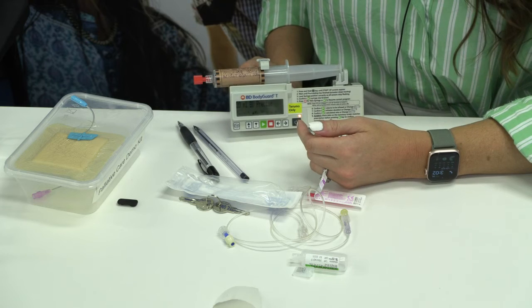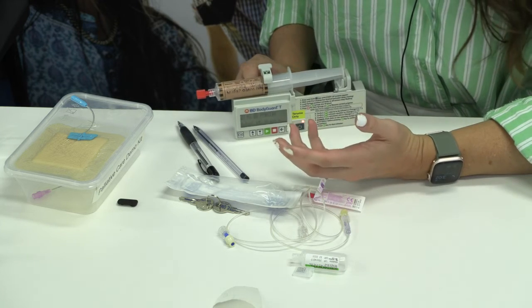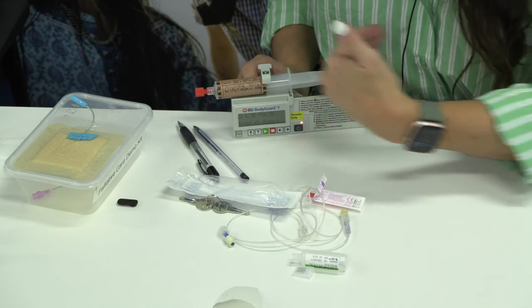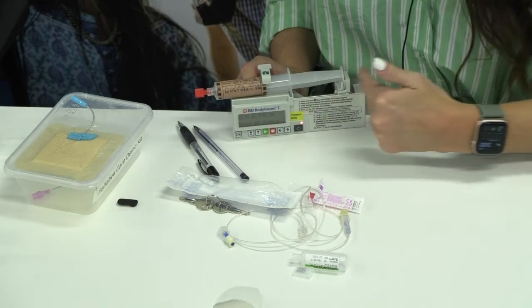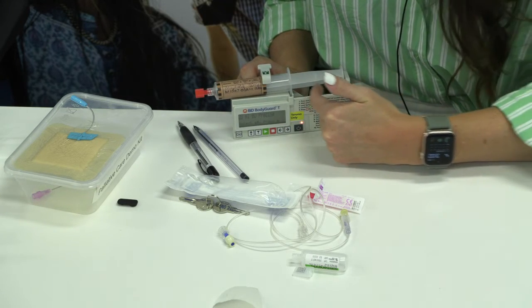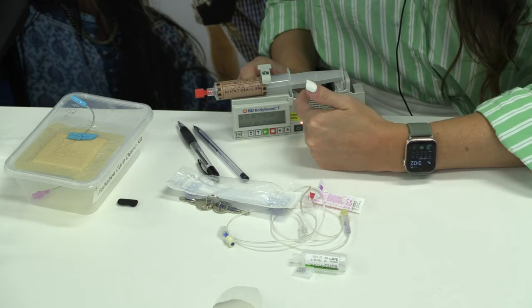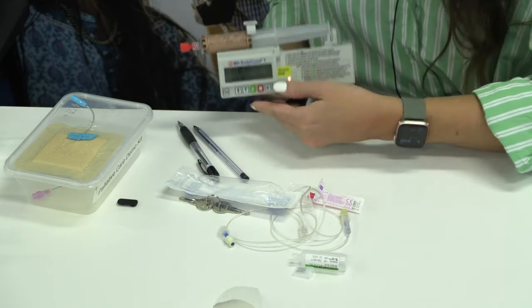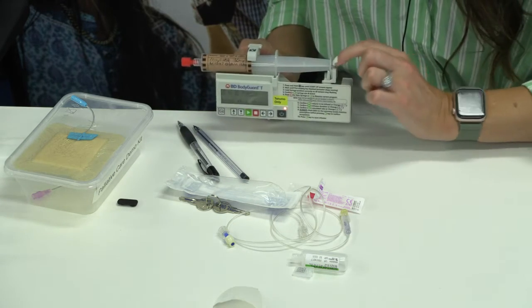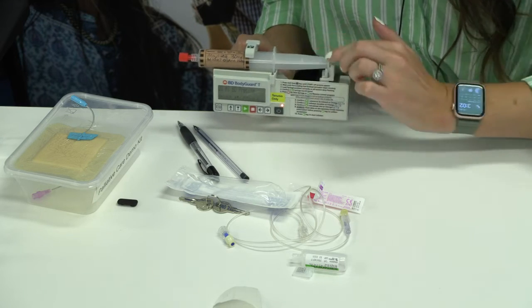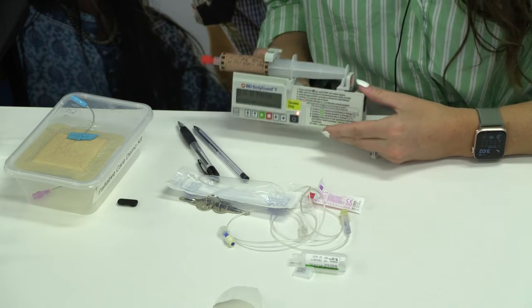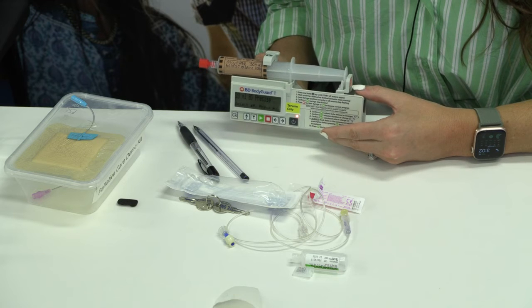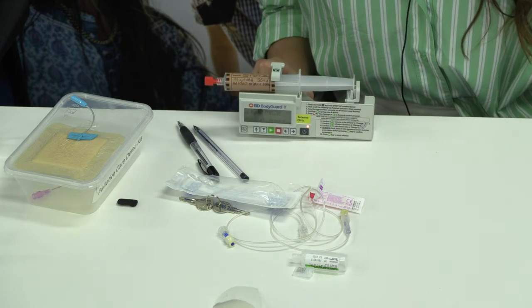So what do I have here? Yep, it tells you to wait for the automatic preload. But as I mentioned, you may need to move it back or forward. Sometimes the pump, the actuator, will move all the way forward, and you just press the backwards arrow to get it to move back. As long as you can fit both within there, the machine allows you to do that.